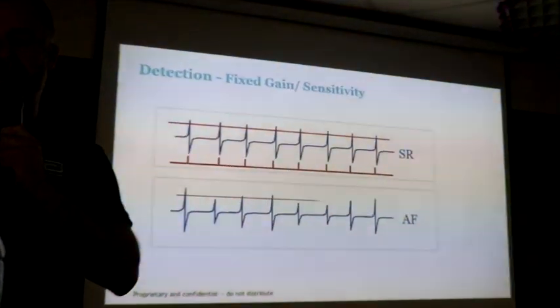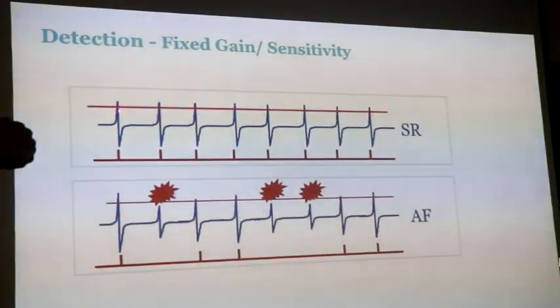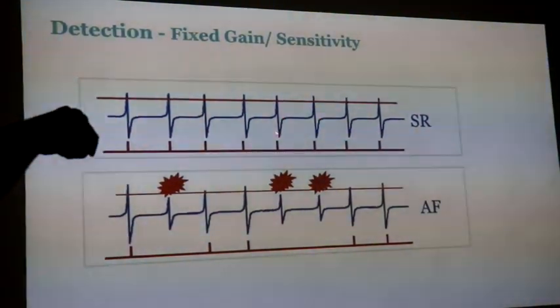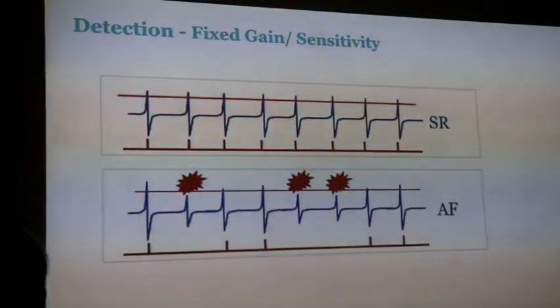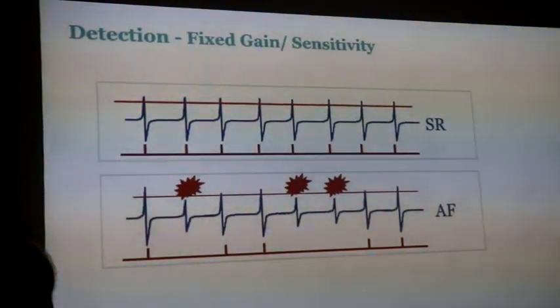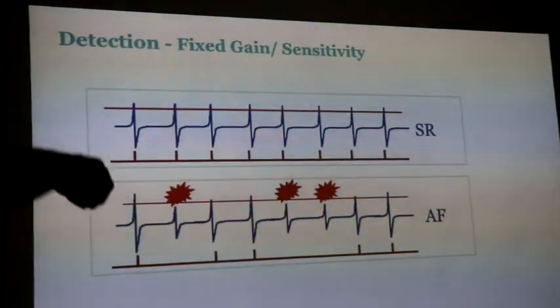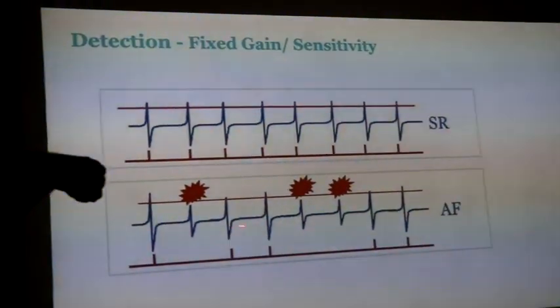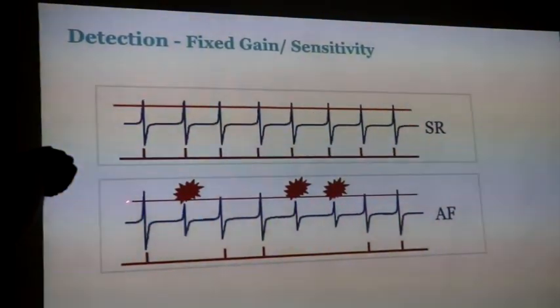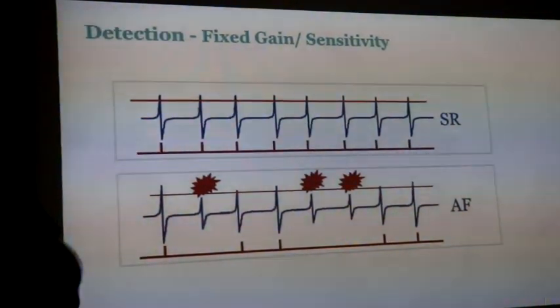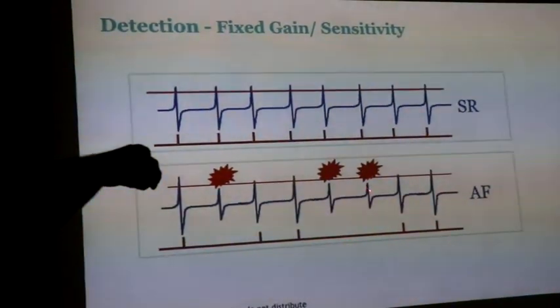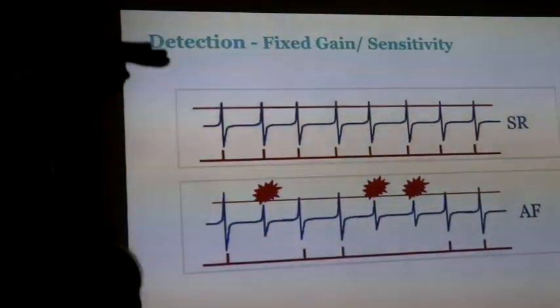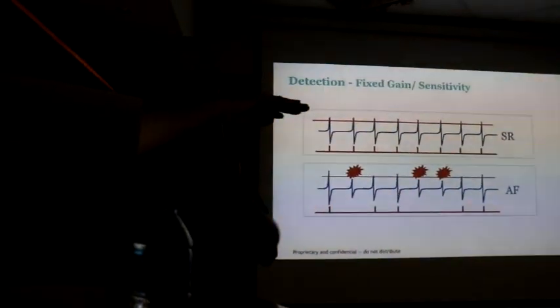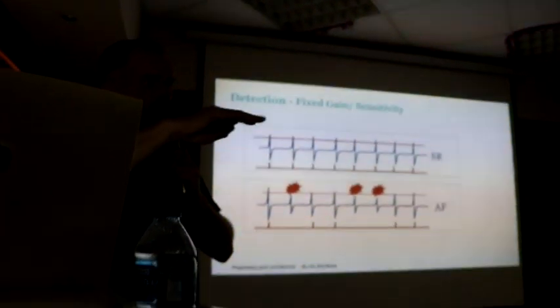So what we normally have, moving through this quickly, is a fixed sensitivity for the RV lead. This is a ventricular lead, and normally it's fine, because in pacemakers the R wave signal is the same, no problem. We set it at 2.5. This is an atrial signal, not an RV signal, the atrial signal in AF. And what you see is very changing cycles and amplitudes, so you can miss things, and all of these could be below the maximum sensitivity. So typically we set the atrial sensitivity at maybe 0.75 of a millivolt to 1 millivolt, but signals can be smaller than that, so we would undersense AF.